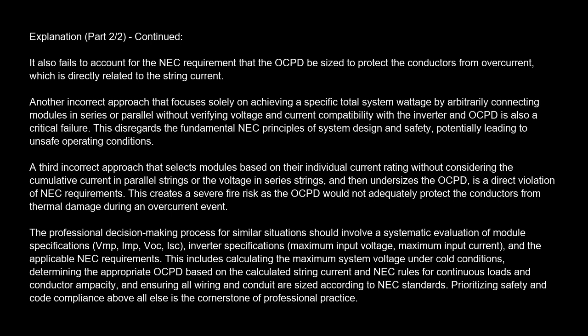Another incorrect approach focuses solely on achieving a specific total system wattage by arbitrarily connecting modules in series or parallel without verifying voltage and current compatibility with the inverter and OCPD. This is also a critical failure. It disregards the fundamental NEC principles of system design and safety, potentially leading to unsafe operating conditions.